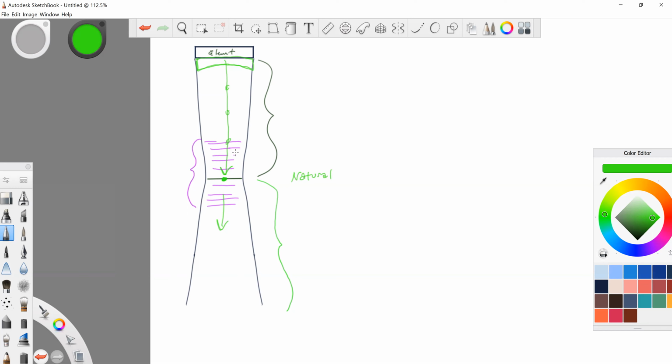Let's go through 309 through 317 quickly. The near zone is the only region where the diameter of the sound beam is smaller than the transducer's. Well, I would say everything up until, so here's my original aperture up here. That's at 2 near zone lengths.